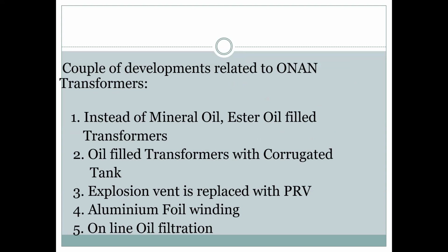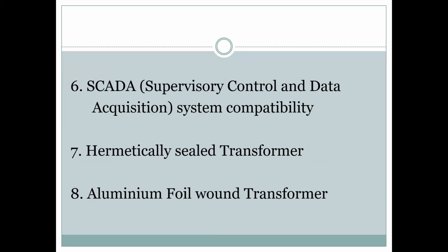Instead of mineral oil, we now come with ester oil. This is the next generation transformer, the ester oil. There are two types of ester oil: one is natural ester oil, and one is synthetic ester oil. This basically increases the life of the cooling medium, so that you need not take the transformer out for this. Hermetically sealed transformers are there. You don't need to do anything. Aluminum foil transformers, I have already said about it.